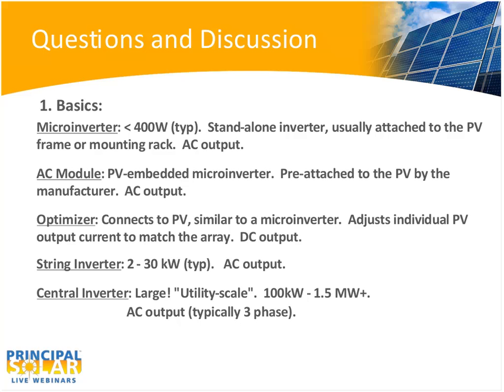Microinverters all have grid-ready AC output. AC modules are, in fact, a microinverter, but they are PV embedded. The National Electric Code, Section 690.2 and .4, delineates specifically the definition of an AC module. It is a permanently attached microinverter, attached to the PV by the manufacturer. Whether that's done by the PV manufacturer or elsewhere, it does not matter. It is marketed as a complete unit with PV and inverter attached. Like the microinverter, it too has strictly AC output.